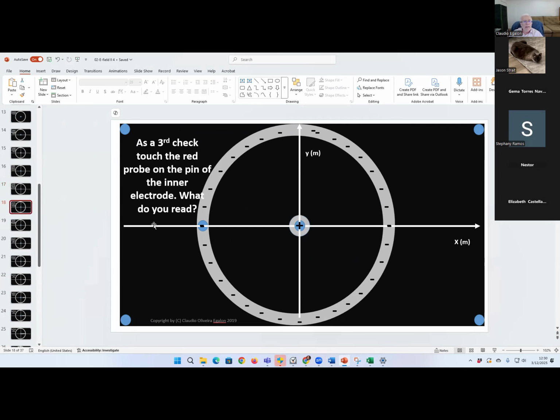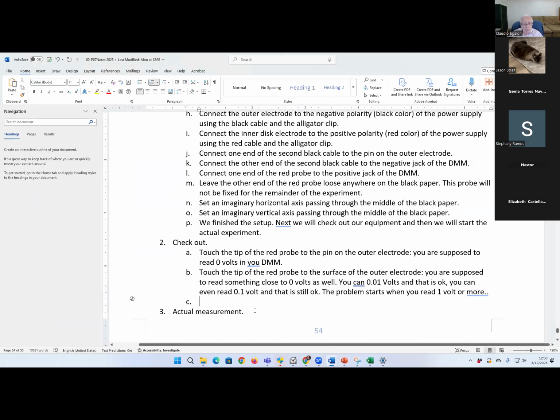Next, as a third check, touch the red probe on the pin of the inner electrode. Now you're going to get the red probe. You're going to touch the pin here at the very middle. The black probe is going to be touching the pin of the outer electrode. The red probe is going to touch the pin on the inner electrode. Okay? And if you do that, you should be able to read 10 volts. Okay? Third check.